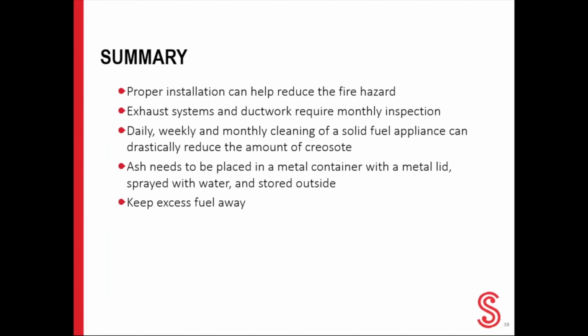All right, so let's recap. The main hazards of solid fuel cooking are fire and creosote. Proper installation of solid fuel appliances can help reduce the fire hazard. Exhaust systems and ductwork covering the solid fuel cooking appliance require monthly inspections and cleaning if necessary. To reduce the amount of creosote in a solid fuel appliance, daily, weekly, and monthly cleaning is needed. Ash needs to be placed in a metal container with a metal lid, sprayed with water, and stored outside. And any fuel greater than 1 day's worth must be kept far away from the cooking appliances.